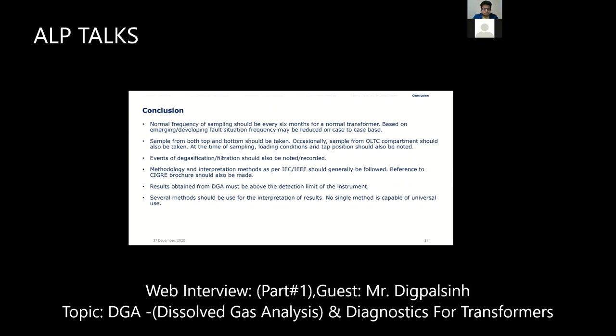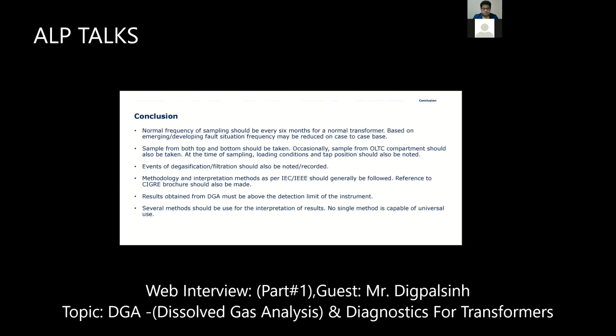If your transformer is healthy, then you just have to define the frequency at 3 months or 6 months interval. 6 months is better for a normal transformer. You always go with DGA every 6 months. Yes, that would be good.